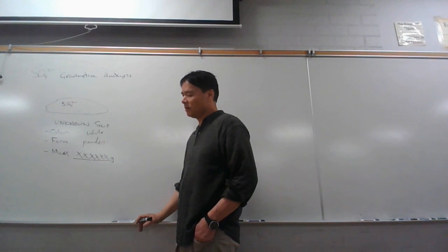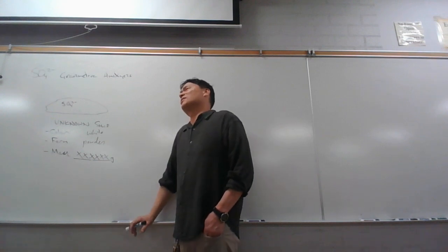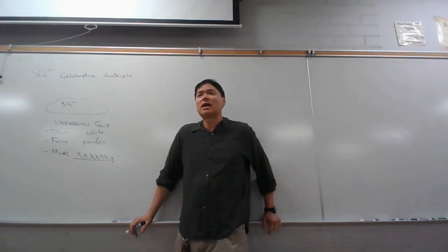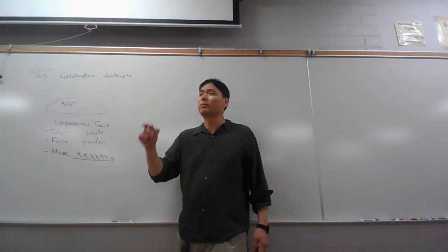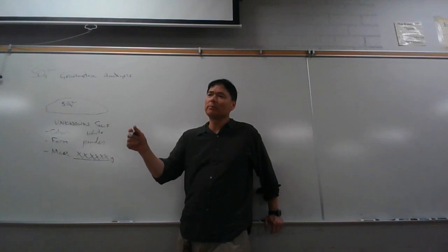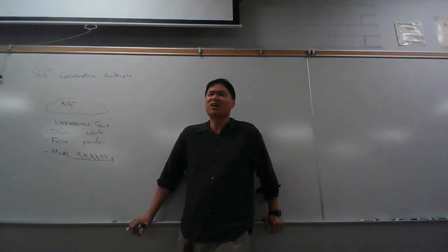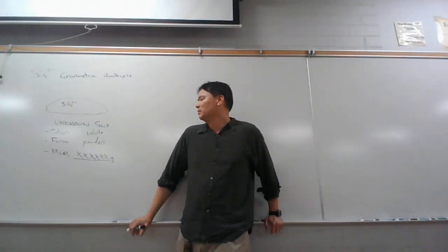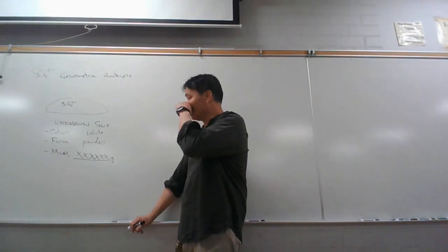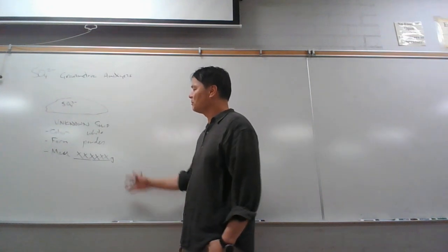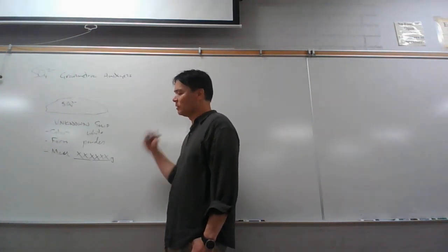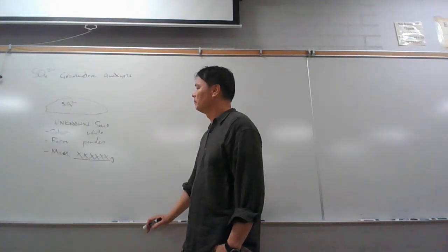We have the moderately expensive standard masses, I think it was like $200 for the set. And so we can just go over there and make sure it's reading properly. So when we zero it, we put the standard mass on there, 10 gram, 100 gram, whatever, and see if it's reading. If it's not reading correctly, then we'll adjust the calibration to make sure it's reading correctly. You don't have to calibrate the balances. The balances have already been calibrated for you.